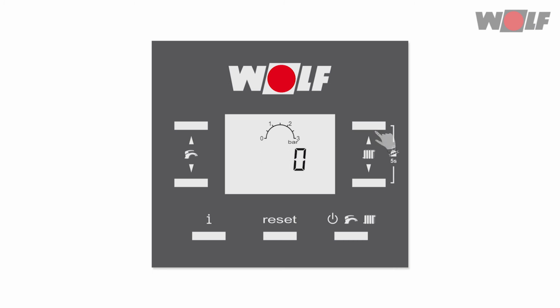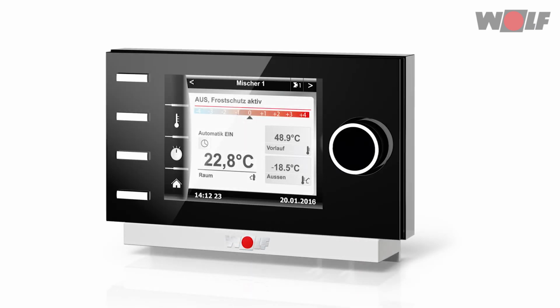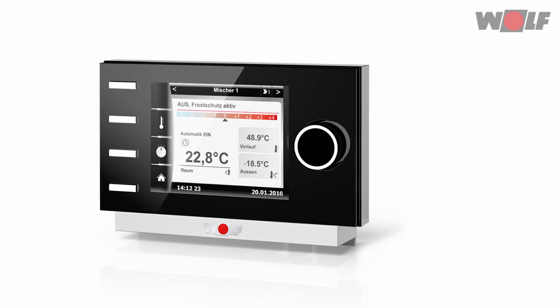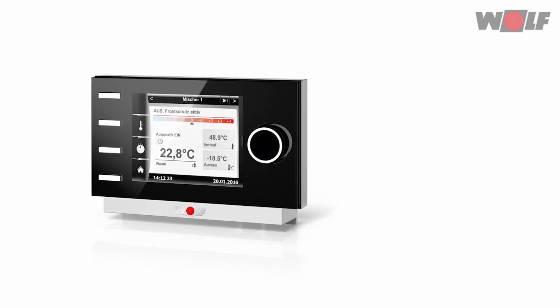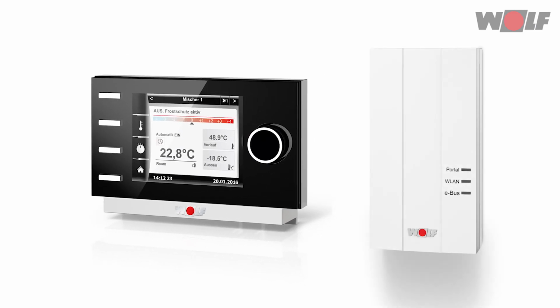Parameter H54. If the heating curve is greater than 0, the setting for the heating flow temperature via both the heating buttons up and down is disabled. The FGB boiler can be combined with a BM2 to a remote control. The operation is very comfortable and convenient. Combined with the external interface module ISM7E, the device can be operated online with LAN or Wi-Fi via eBus.